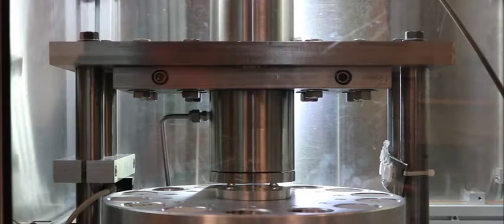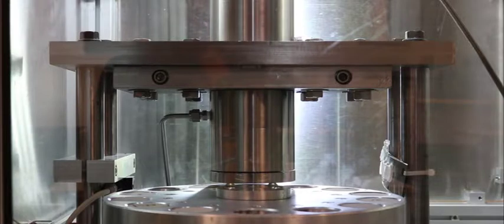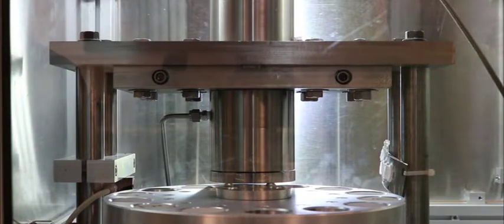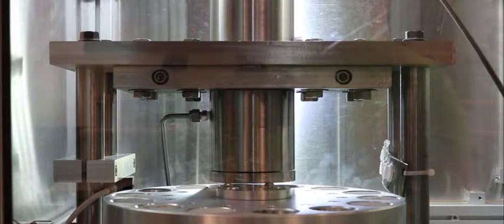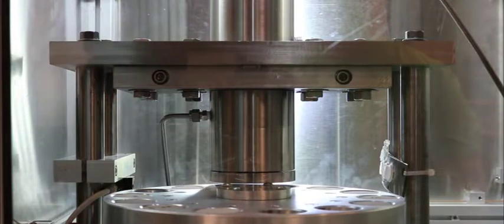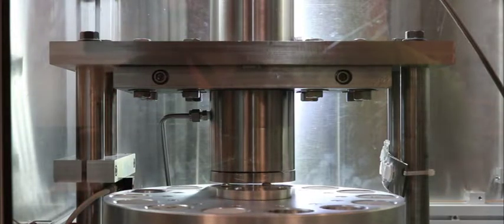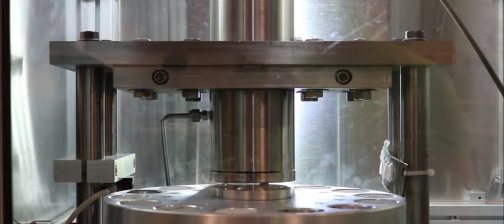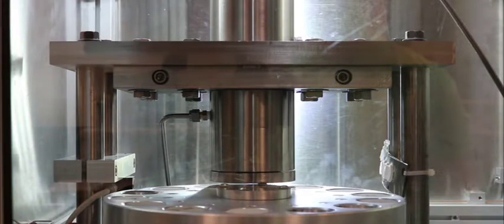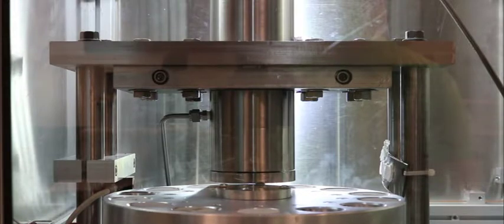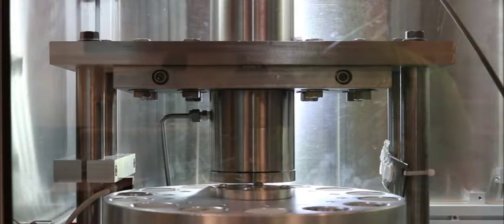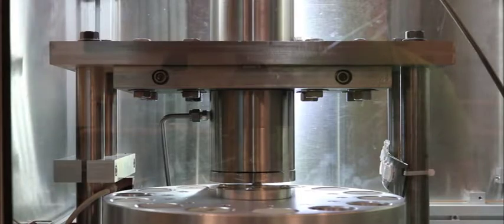When testing for a particular sample is complete, if there are subsequent samples to be tested, the APDP-HP101 auto-test feature will automate the procedure of releasing the tested sample from the chamber, returning it to its original place within the carousel, rotating the carousel and repeating the entire procedure for the following sample. When using the auto-test feature for testing and data acquisition, no user interaction is necessary.